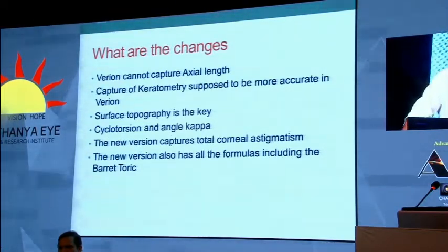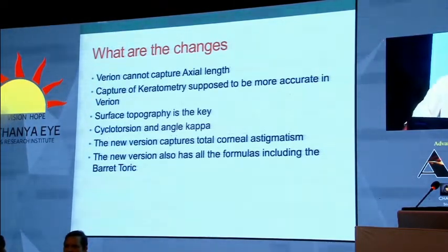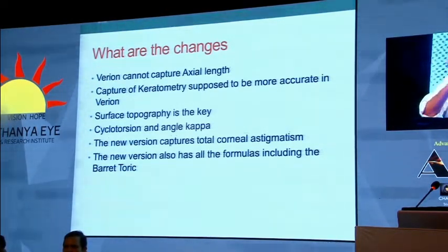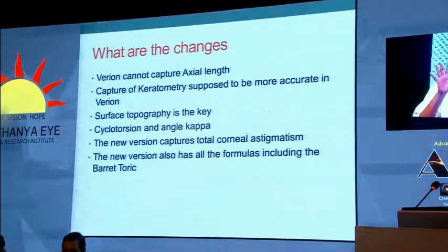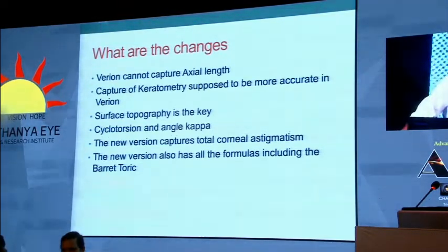What are the changes we are looking at? The Verion cannot capture axial length as of now, so you have to depend on your Lenstar or IOLMaster or whatever is available to calculate axial length. The keratometry capture is supposed to be much more accurate with the Verion, which is why it gives more predictable results. The surface topography is the key — the way the surface is mapped, the way cyclo torsion is managed, the way angle kappa is measured, and the misalignment between the optical and visual axis. These are the things that make the Verion a much more accurate machine with much more predictable results.